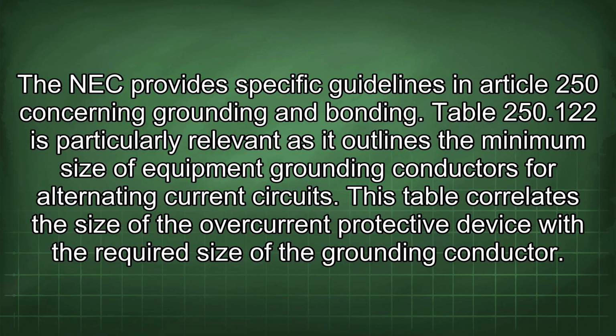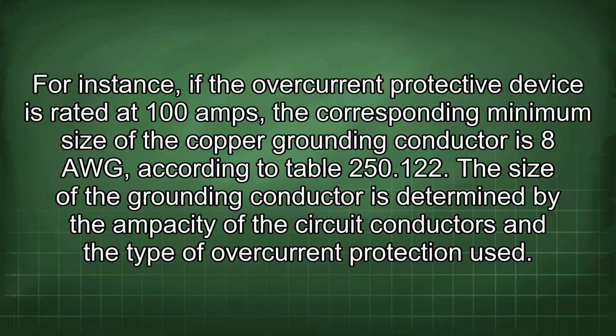Table 250.122 is particularly relevant as it outlines the minimum size of equipment grounding conductors for alternating current circuits. This table correlates the size of the overcurrent protective device with the required size of the grounding conductor.